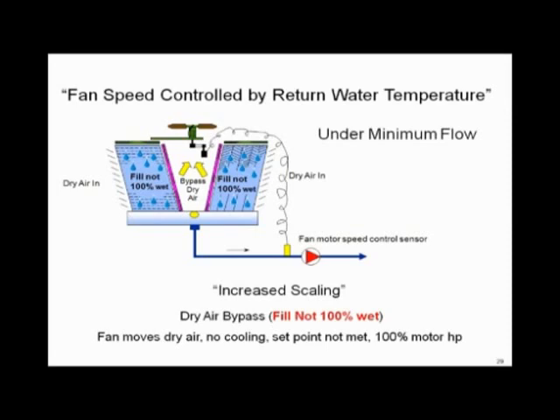Here's what happens when you underflow a cooling tower — when you don't put enough water flow and operate below the minimum turn down. You've got fans trying to maintain 85°F condenser water with a variable speed drive, controlling fan speed to maintain 85 degrees going back to your condensers. But if you don't put enough water into the hot decks to keep the fill wet, you get dry air coming in from both sides with a lot of fill sitting there not wetted.